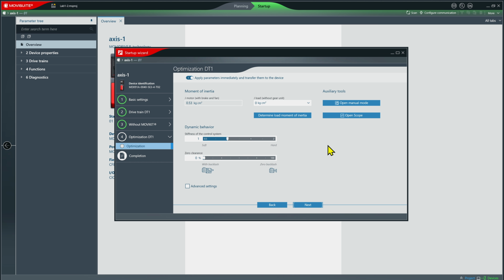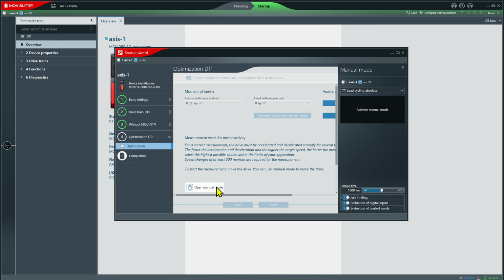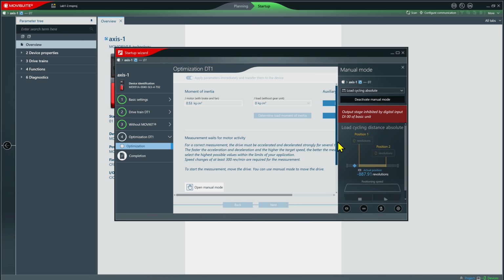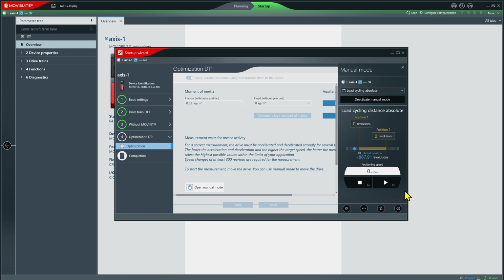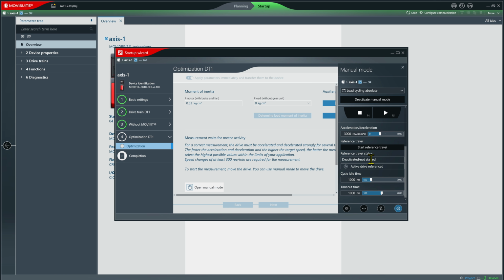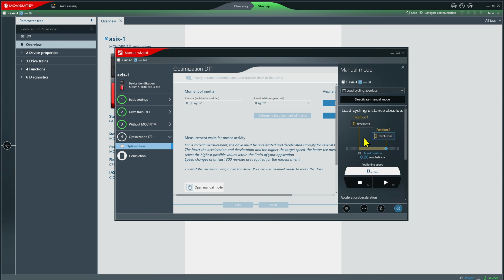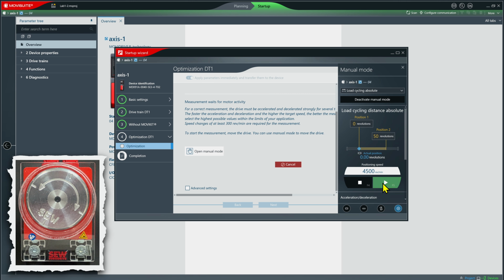And again, we've got to determine the inertia, so we need to tune our drive. Let's do that. I click Determine Load Moment of Inertia, open manual mode, activate it. Got to remove Controller Inhibit. I need to open my extra settings here and scroll down and reference my drive. I also need to set my acceleration slider to maximum. And I need to set my positions between 0 and 50 revolutions and my motor speed 4,500 RPM. There we go. We're now ready to take some measurements.